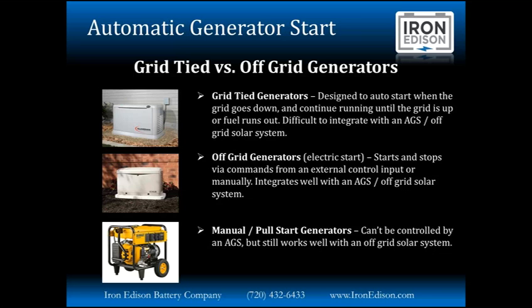The generator is going to start up instantly, or maybe a slight delay depending on how it's programmed, and then switch the transfer switch over so that the generator is powering all of your loads, and then it's just going to keep monitoring for the grid to come back. And once the grid does come back and it's qualified, it'll flip the transfer switch back over to the grid and shut the generator off.